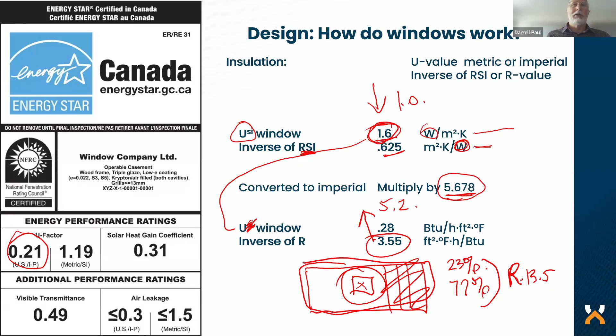So which materials should I use and how should I use them? Well, when we talk about low E, it's the coatings that go on the window. And they're basically a silver coating that's microscopically applied in either a single, double, or triple layer. And as we put them into the multiple layers, we get either better blockage or we let more heat in. So a low solar heat gain window will have 3 layers of silver coating, blocks heat nicely. A single layer or a high solar gain window will let lots of heat in.